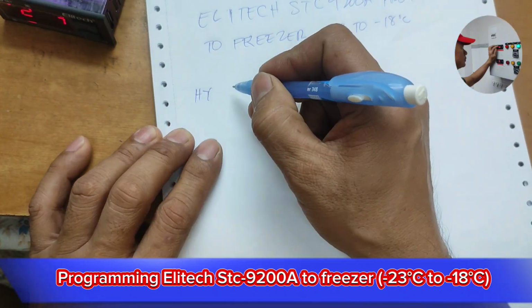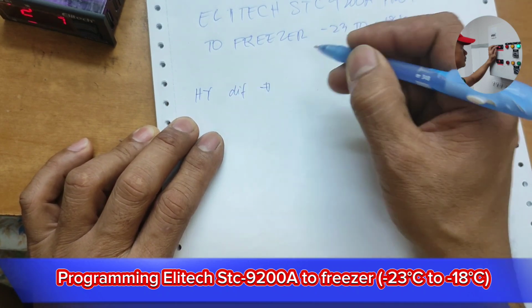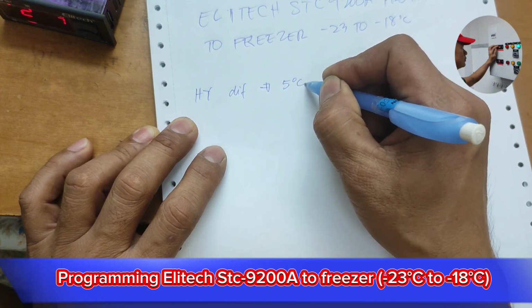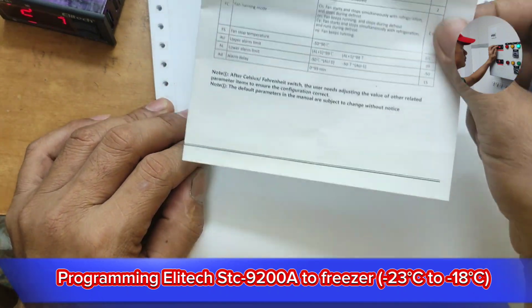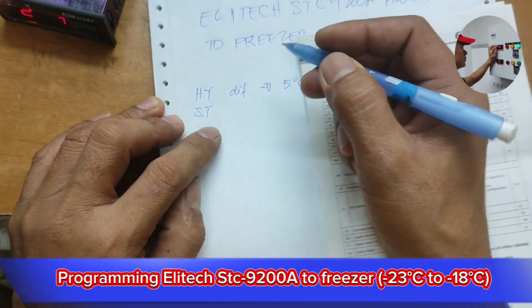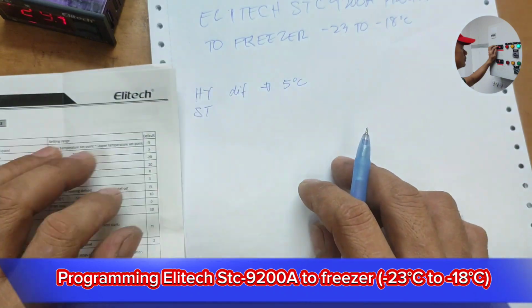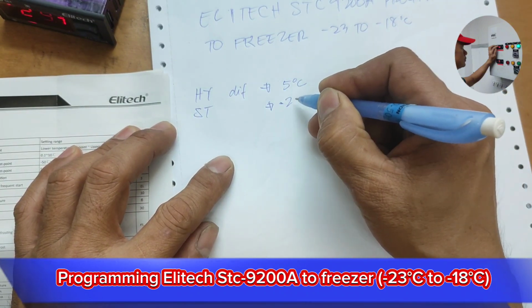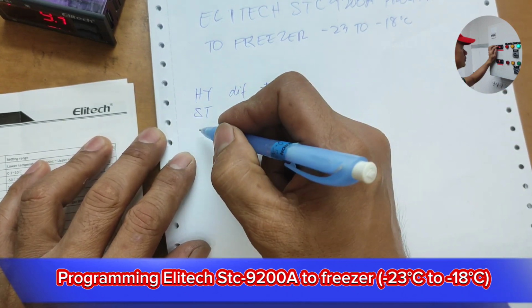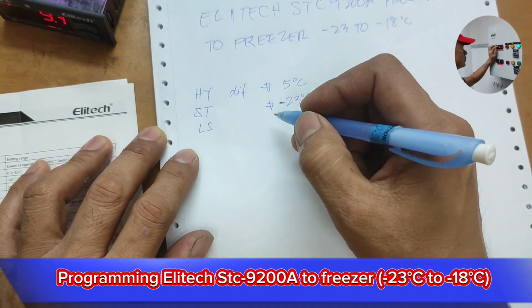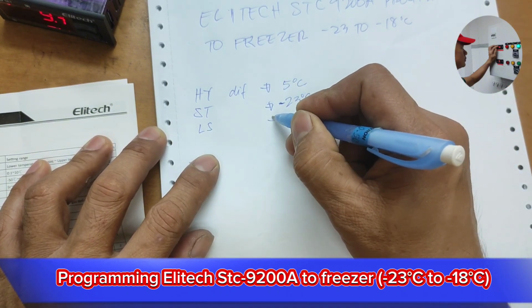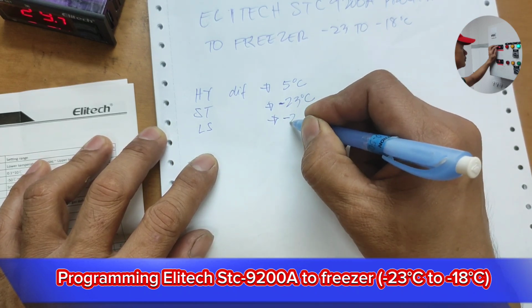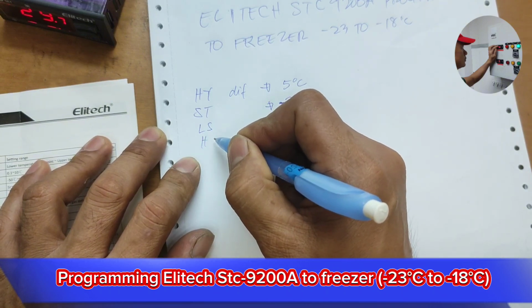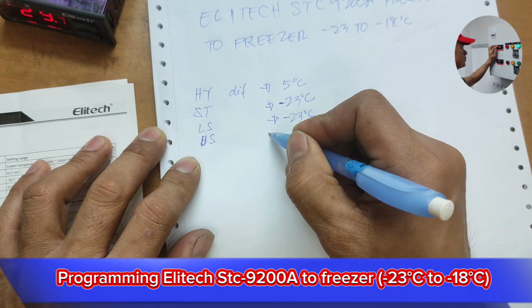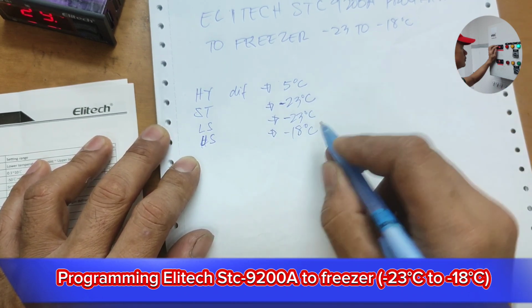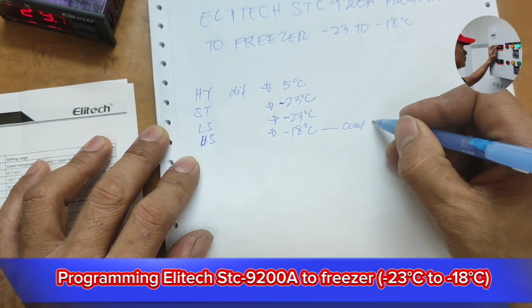The HY is the differential, and this differential we put to 5 degrees Celsius. I also program the ST. ST is the set point, and our set point is negative 23 degrees Celsius. Our LS, which is the lowest set point, is the same as my set point, which is negative 23. And my HY, no, my HS, I mean, is set to negative 18. At this stage, the compressor will turn on.